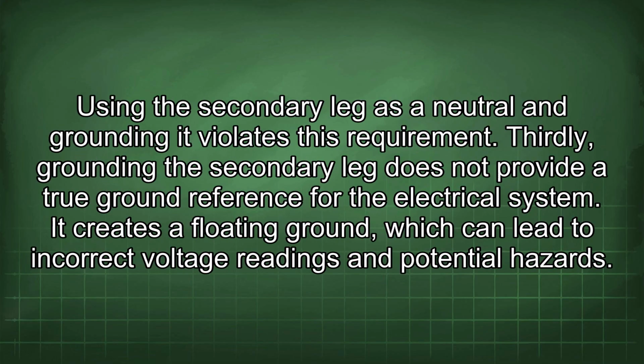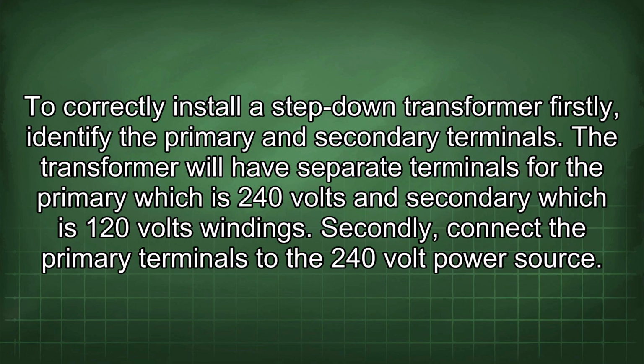Using the secondary leg as a neutral and grounding it violates this requirement. Thirdly, grounding the secondary leg does not provide a true ground reference for the electrical system. It creates a floating ground, which can lead to incorrect voltage readings and potential hazards. To correctly install a step-down transformer, firstly, identify the primary and secondary terminals. The transformer will have separate terminals for the primary, which is 240 volts, and secondary, which is 120 volts windings.